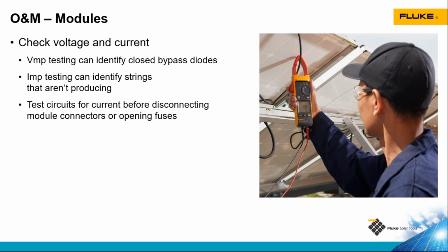There are at least two types of disconnects in solar that are non-load break rated. They cannot be opened when current is flowing through the circuit. These include our module interconnects like Stäubli MC4 connectors. Also, our touch-safe fuse holders are not designed to be opened under load. So if we're doing maintenance or troubleshooting operations on a section of the array, we've shut that section off. Before we open any of those connectors, we need to check to make sure there's no current flowing through the circuit. If there is current flowing through the circuit and we open up one of those quick connectors or a fuse holder, it's going to arc, it's going to cause damage to the connectors or the terminals, and it's going to be a safety hazard for the technician.